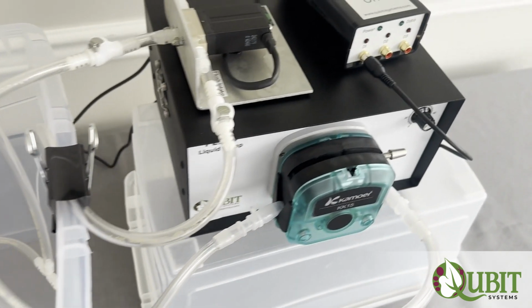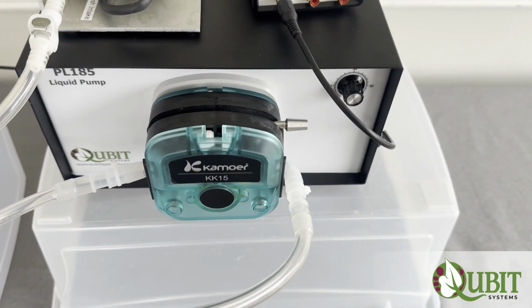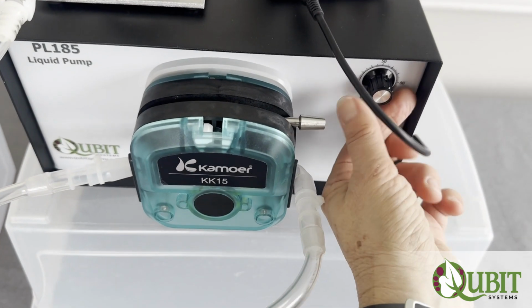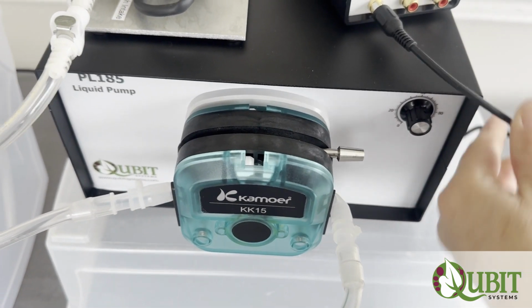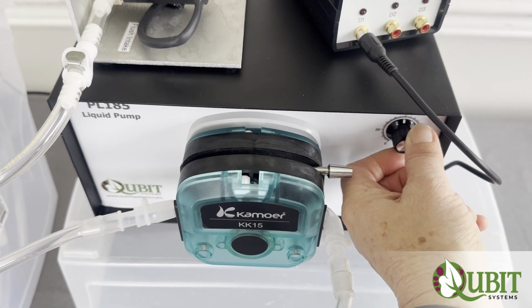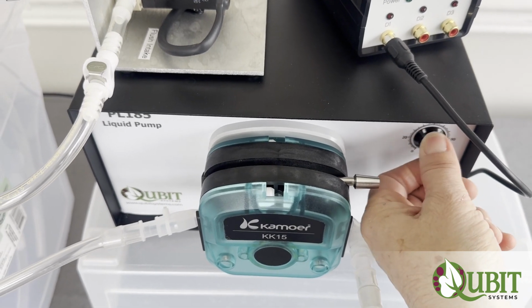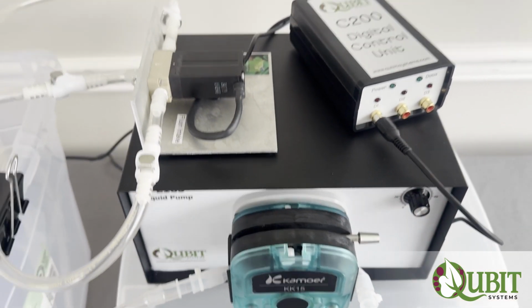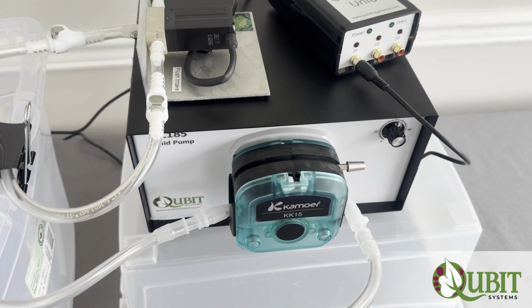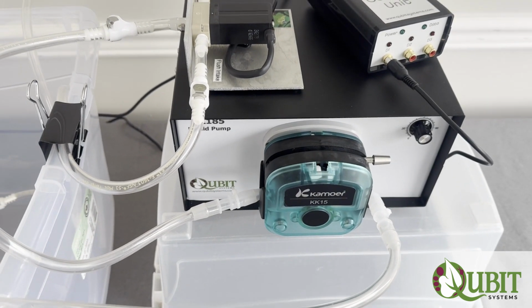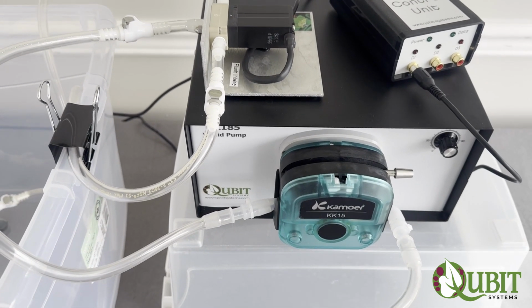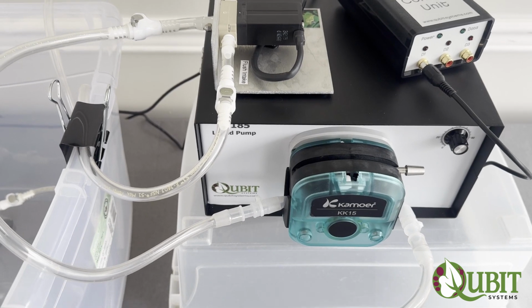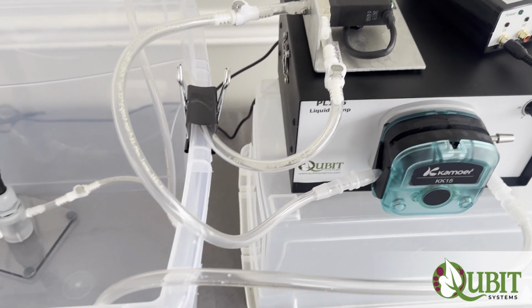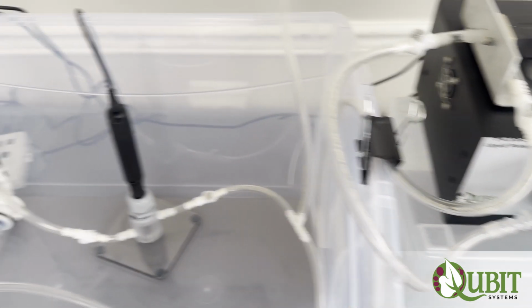This is useful because the flow of the water is set up through changes in the speed of this pump here, and the flow rate is directly proportional to the analog output from the pump, and the user can calibrate that output for their particular system when initially setting it up, so they know exactly what flow rate is being provided to the respirometer chamber.